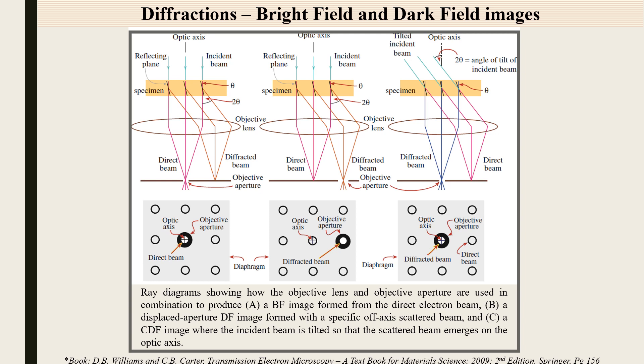For practical imaging, there are three examples. To get a bright field image, the direct beam is directed toward the objective aperture — the direct beam going through gives the bright field image. For a dark field image, the objective aperture is displaced to block the direct beam and instead select the diffracted beam through the objective aperture, giving a dark field image.